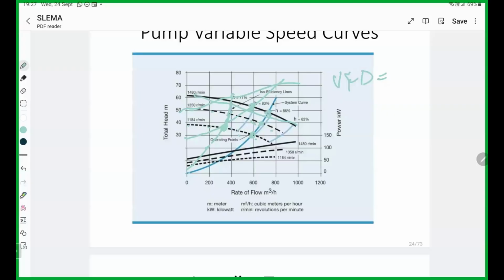You have to keep in mind, that is also important, VFD suppliers always say we can save energy by using a VFD, but it is ideal only when the system is a closed system, where the ISO efficiency curve is changing very evenly. But if the system curve is flat, then our efficiency may decrease, and the power energy consumption after VFD installation may increase.